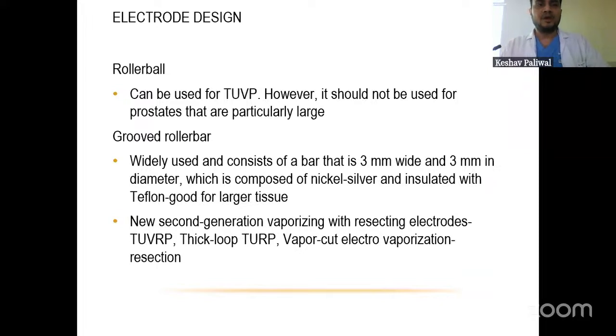The two types of electrode designs are there. Roller ball can be used for TUVP. However, it should not be used for prostates that are particularly large. It cannot be used for larger prostates. And a grooved roller bar is widely used, which consists of a bar that is 3 mm wide and 3 mm in diameter, composed of nickel silver and insulated with Teflon.